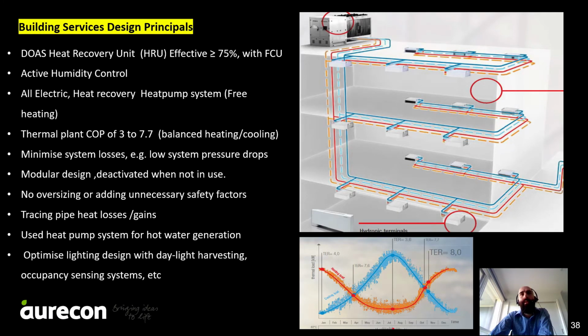The main HVAC and building services design principles that we applied to this project were using chilled water and heating hot water fan coil units with a direct outside air system, incorporating heat recovery units with minimum efficiency of 75%. We included active humidity control in high occupancy areas, and an all electric high efficiency 4-pipe heat pump system was used with an integrated heat recovery system. You would expect COP ranging between 3 to 7.7.